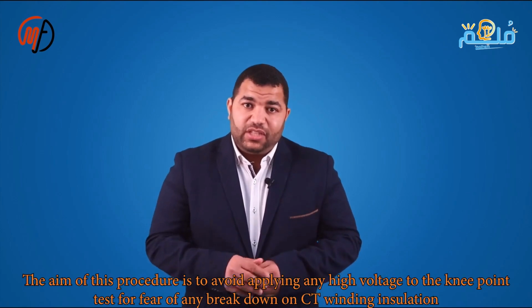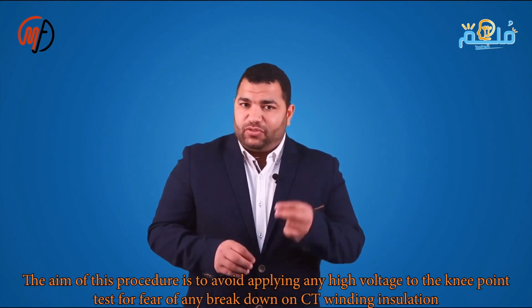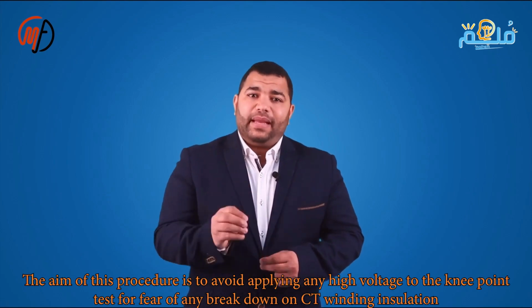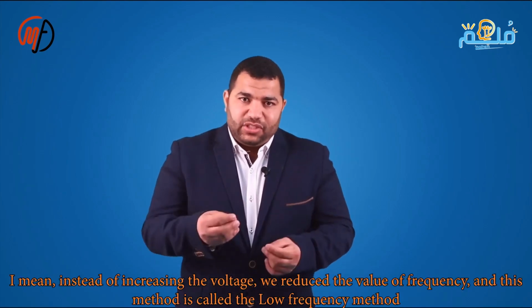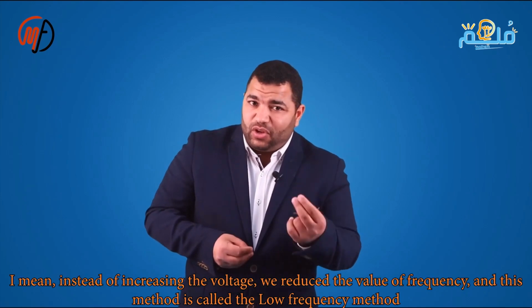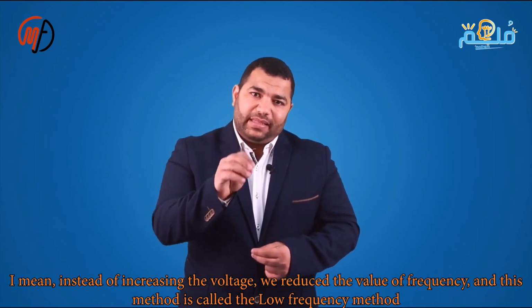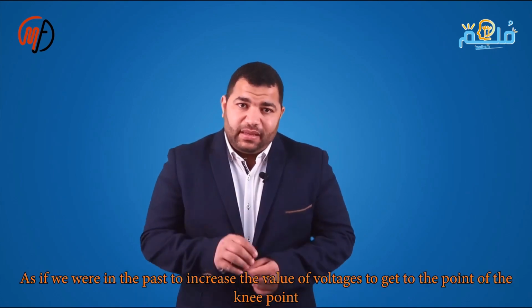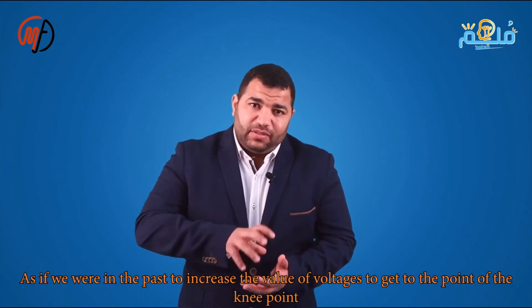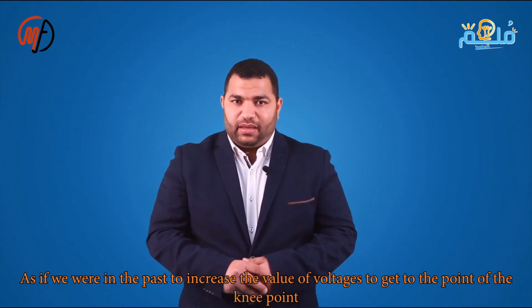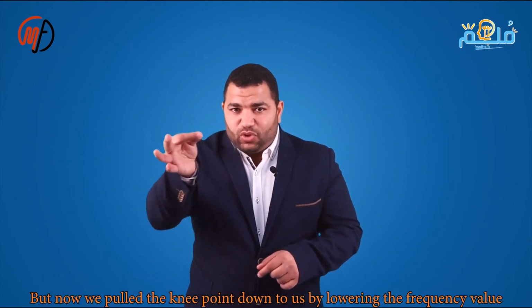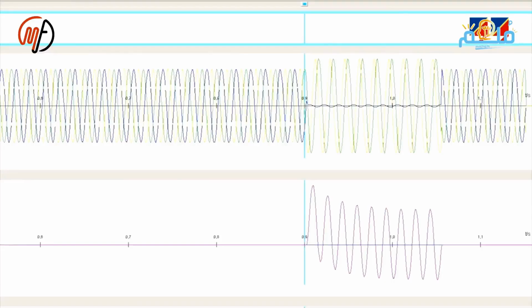The goal of this discussion is to avoid applying any high voltage for testing the knee point, fearing any breakdown on the CT winding insulation. Instead of increasing the voltage, we reduced the frequency value. This method is called the low-frequency method. In the past we used to increase the voltage until we reached the knee point, but now we've pulled the knee point towards us by lowering the frequency.